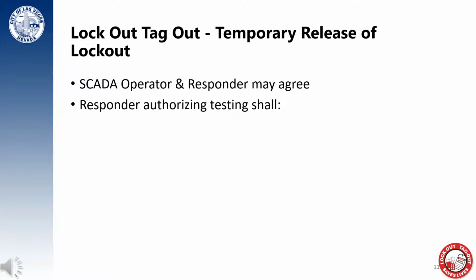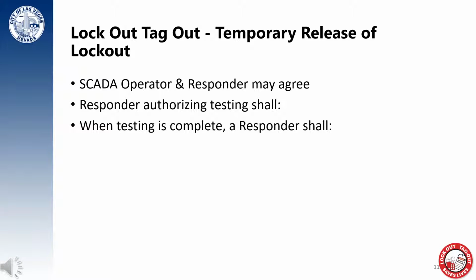Sometimes there will be a need to temporarily release a lockout, usually for equipment testing. If the SCADA operator and the responder agree, then the responder can verify that the equipment is ready for testing. They'll do this by verifying that the employees have removed their personal padlocks and that the equipment can be aligned for testing safely. Once the lockout is removed and testing is complete, the responder shall notify all affected personnel and decide to return the equipment to a lockout tagout state or close the lockout.